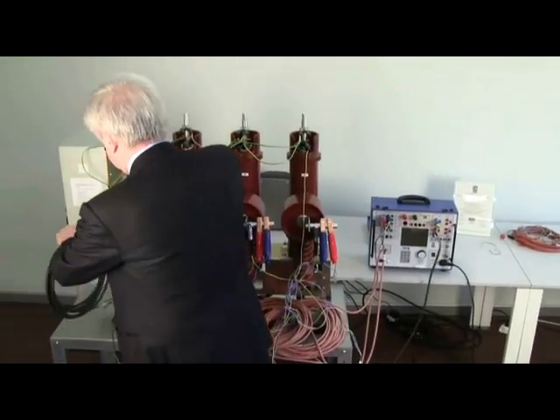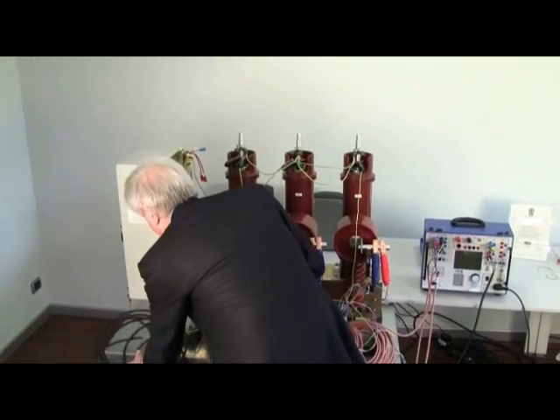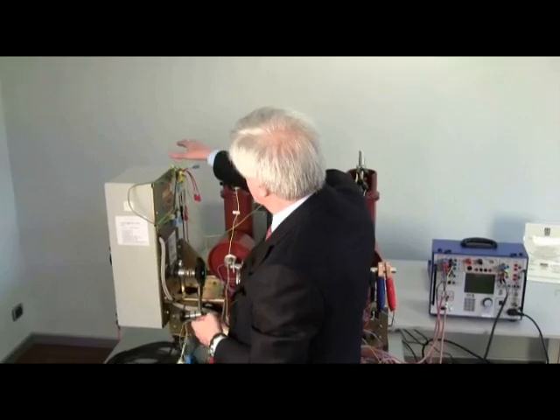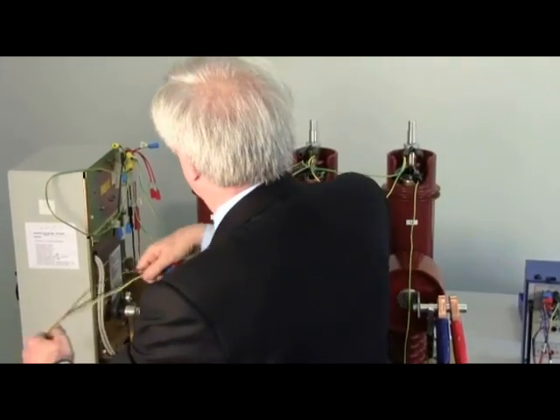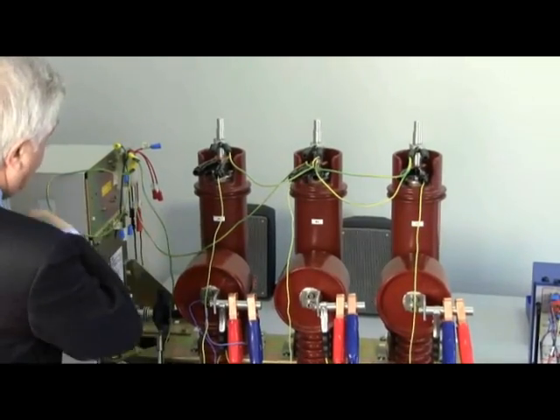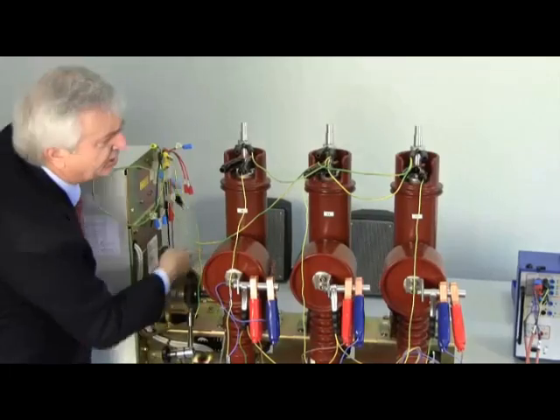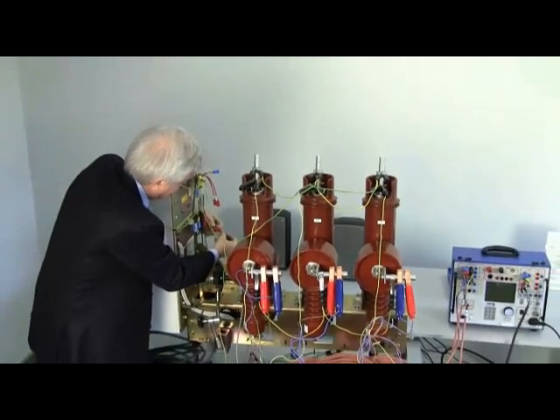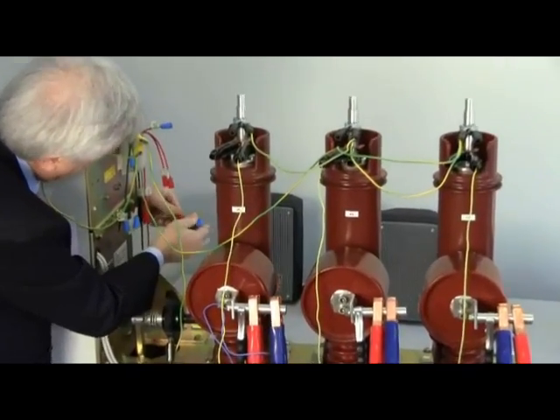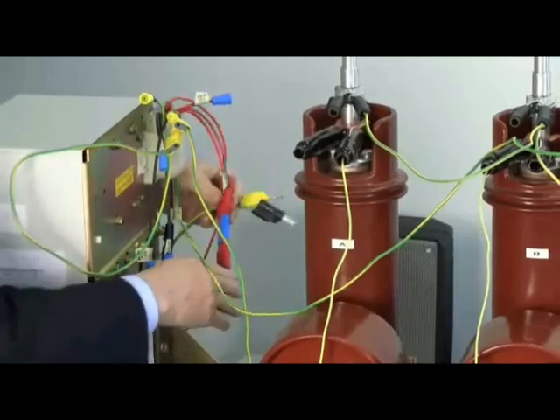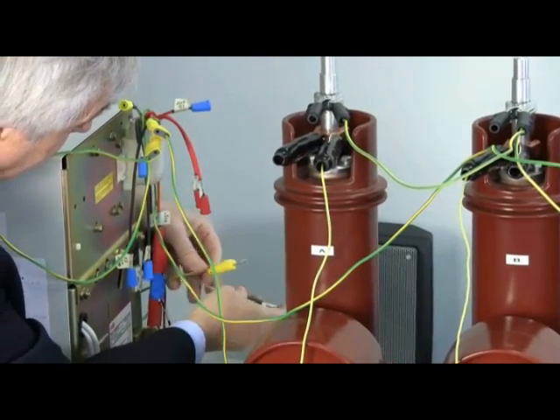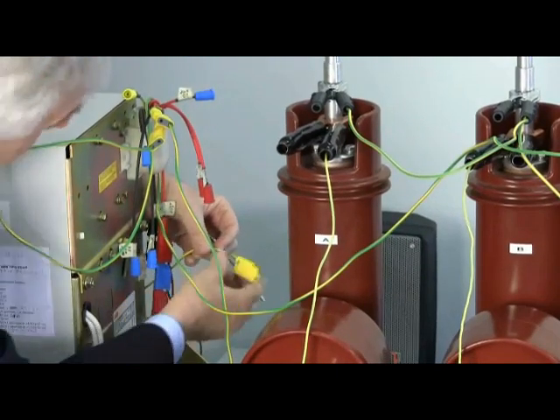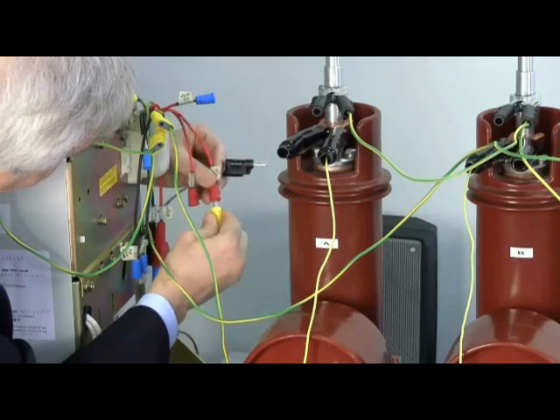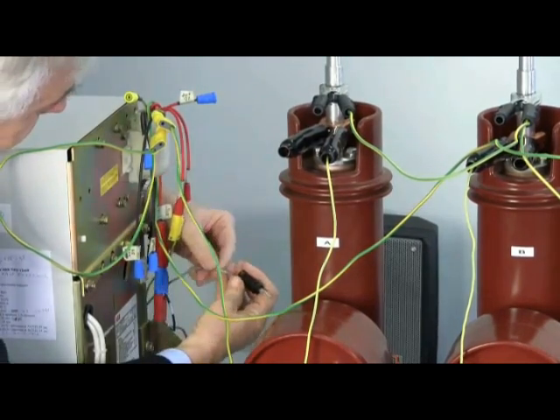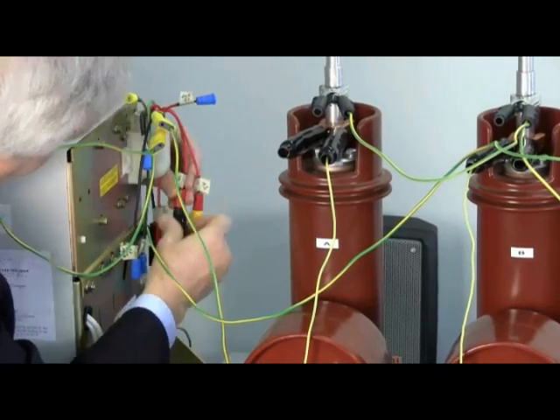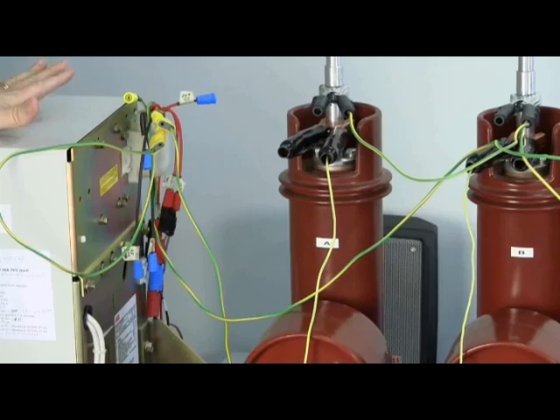Now I come here, and what I have here are the connection to the circuit breaker commands, and in particular to the coil. Well, now I said blue and red, and I connect blue and red to the supply of the circuit breaker, to the positive supply of the circuit breaker, while I connect the open wire to the open command and the close wire to the close coil command, okay? And this is it.